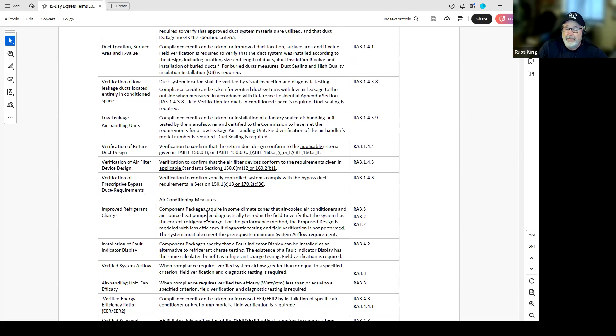Oh, and by the way, as you guys know, the energy code is really encouraging heat pumps, and heat pumps require refrigerant charge verification, no matter what climate zone you're in. Okay, and so that can trigger HERS verification, but it is a prescriptive measure, so you can model it away if you need to. And then heat pumps, especially the mini splits, are very difficult to do a refrigerant charge test. So you have to do the weigh-in test, which requires some special coordination and things like that.